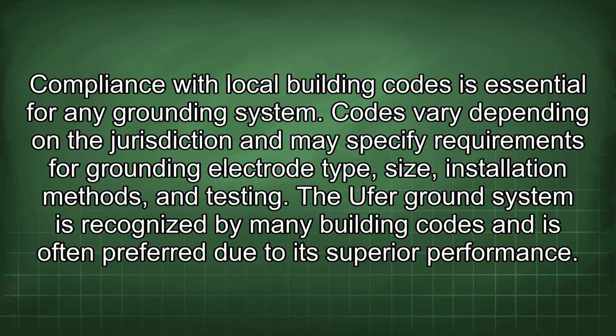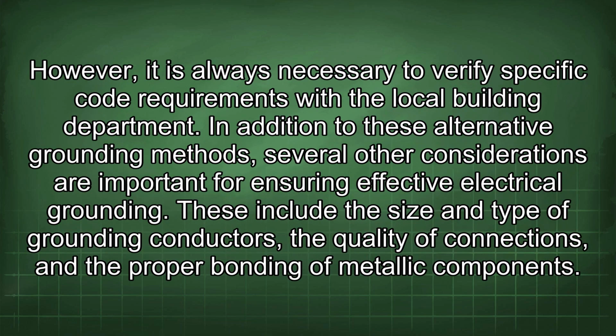Compliance with local building codes is essential for any grounding system. Codes vary depending on the jurisdiction and may specify requirements for grounding electrode type, size, installation methods, and testing. The Ufer ground system is recognized by many building codes and is often preferred due to its superior performance. However, it is always necessary to verify specific code requirements with the local building department. In addition to these alternative grounding methods, several other considerations are important for ensuring effective electrical grounding. These include the size and type of grounding conductors, the quality of connections, and the proper bonding of metallic components.